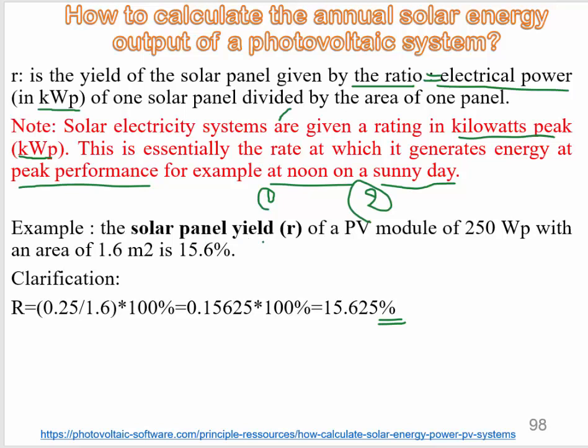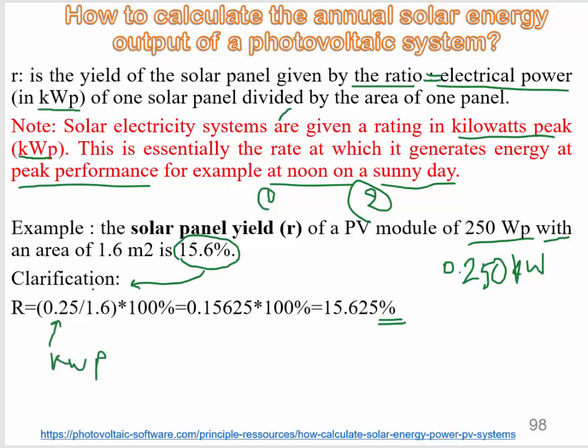Here we have an example: the solar panel yield R of a PV module of 250 watt peak. Be careful — this is not in kilowatt, so we change it to 0.250 kWp, with an area of 1.6 square meters. The calculation is R equals 0.25 divided by 1.6, multiplied by 100%, giving a result of 15.625%, approximately 15.6%.